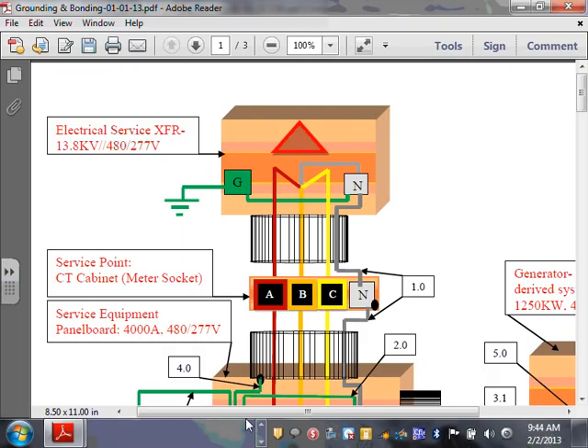Typical example: you have a hospital or government building, or a stadium, and you start with typically 13.8. You guys are familiar with a 13.8 system. A lot of places have 13.8 now. They had 4160, but not a whole lot of places use 4160 anymore. They upgrade to 13.8. You have a 13.8 primary coming as a delta from Xcel or Minnesota Power here, or whatever your utility is, to a transformer provided by the utilities.